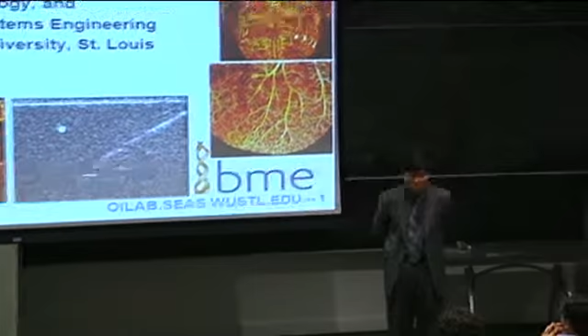This ANSI limit is very conservative because the damage threshold is at least 10 times that level, more or less over 100 milliwatts per centimeter squared. The worst scenario is really dark skin, or dark skin has a lower damage threshold because of the melanin absorption. Does that make sense?